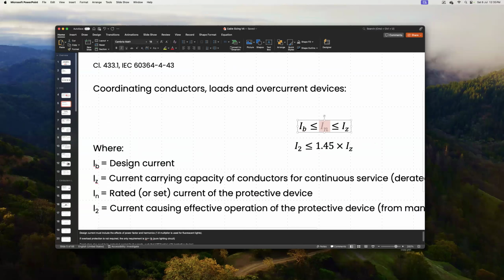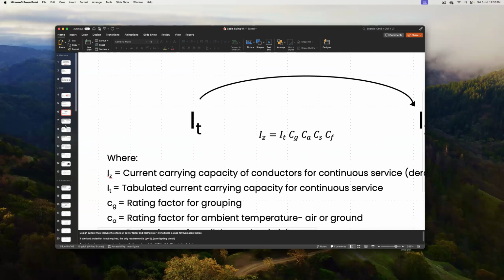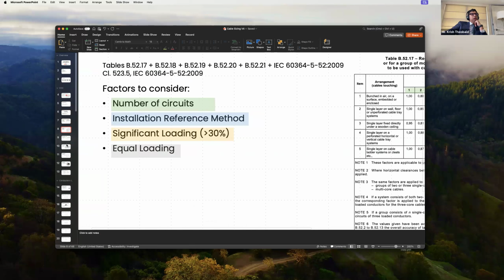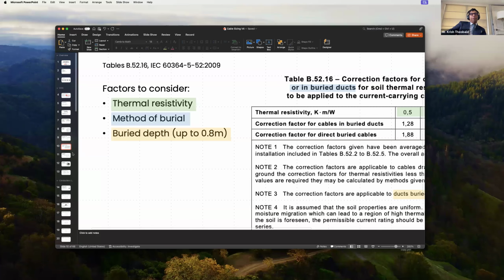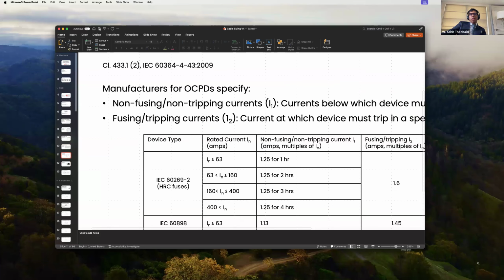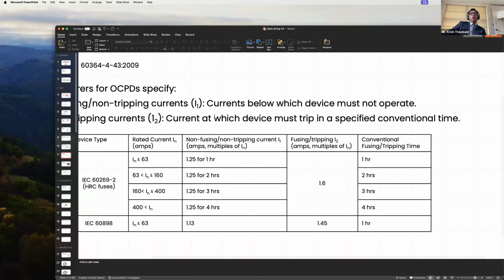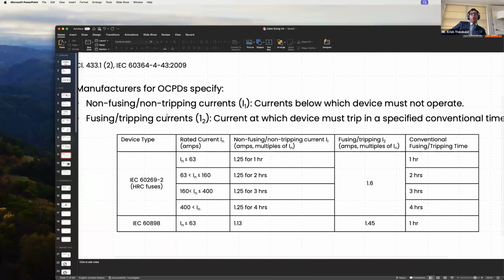Next, how is the fusing factor correlated with protection devices other than fuses? Good question. I know we call it fusing factor, but really there is no actual term given. It is fusing, non-fusing, tripping, non-tripping. For a breaker, it is simply the value at which it disconnects during an overload. Just forget about the word fusing and think about conventional disconnection or conventional tripping current. You're right, it's not limited to fuses.